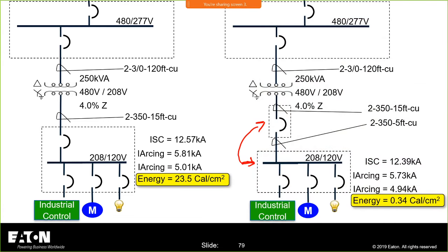Now, a small design change means a lot. I could take that breaker out of that panel board, or leave it in and put another breaker in a box ahead of it, or I could purchase a breaker-enclosed transformer where I include all of that in the same transformer enclosure, and now my incident energy is 0.34 calories per centimeter squared. That is humongous, to go from 23.5 to 0.34 by simply moving the main breaker out of that panel and putting it in its own enclosure. That is a considerable decrease in incident energy.